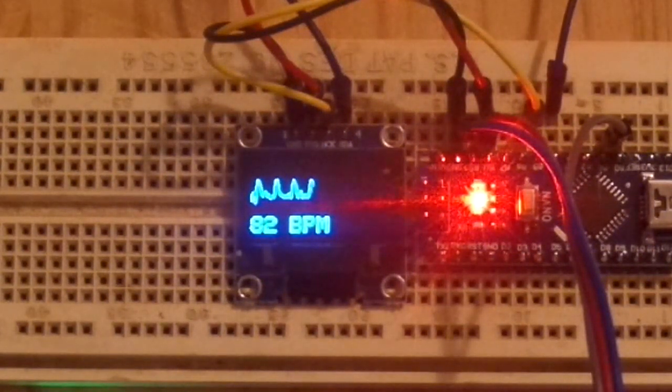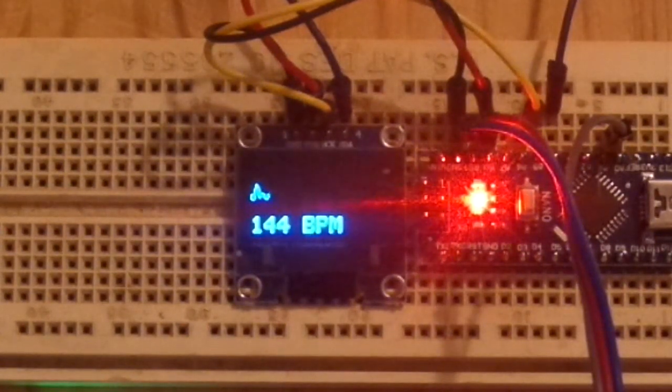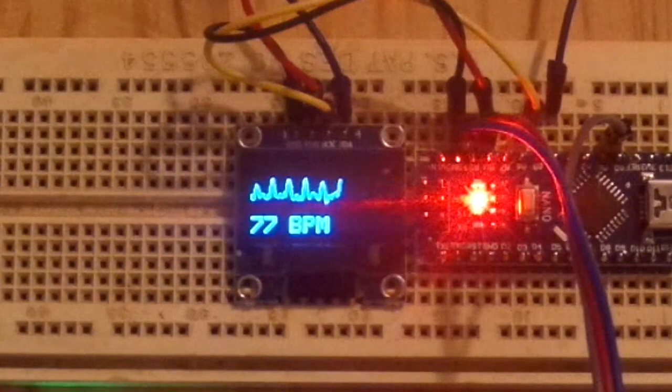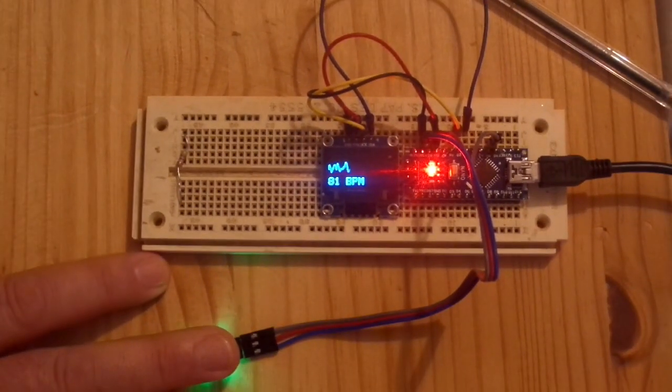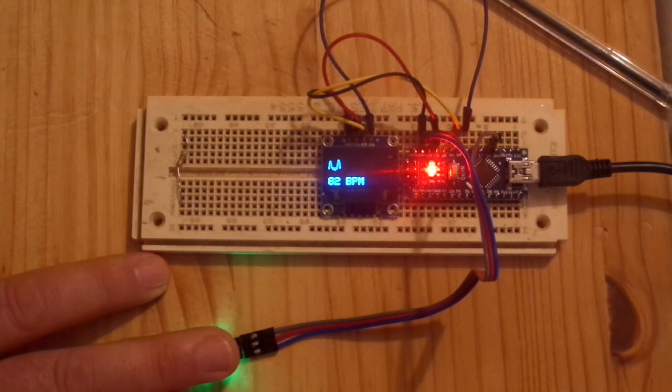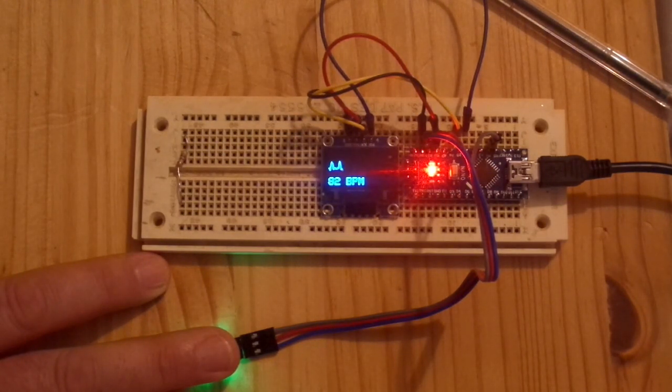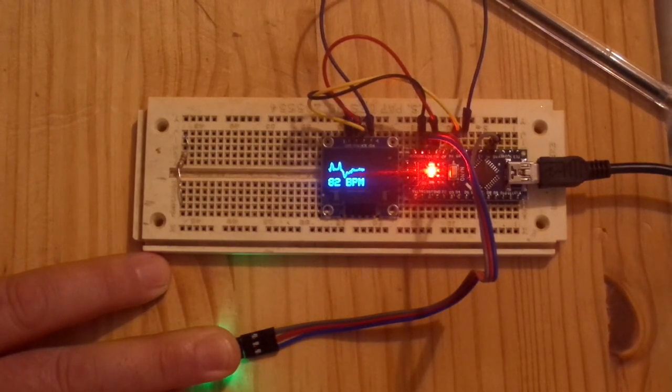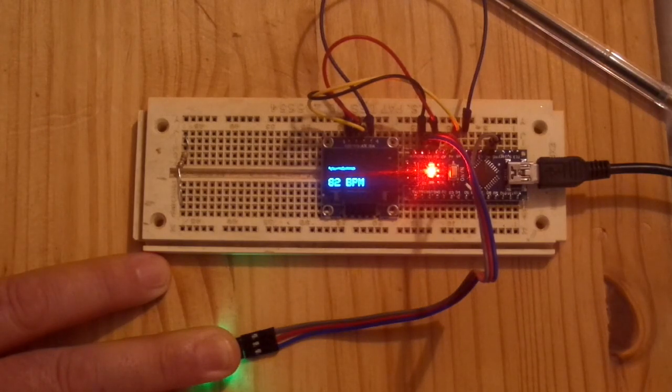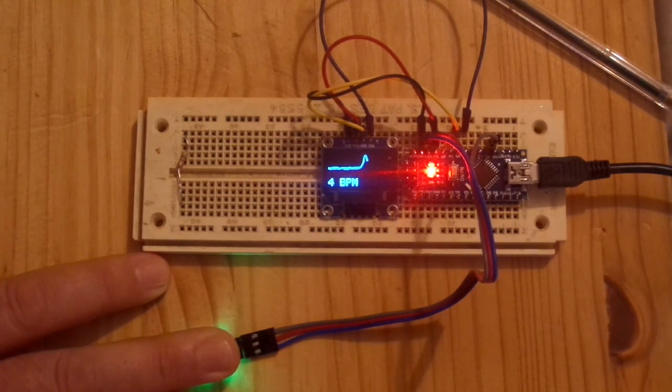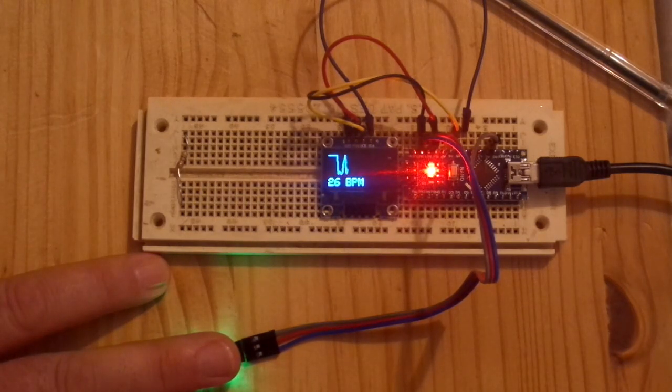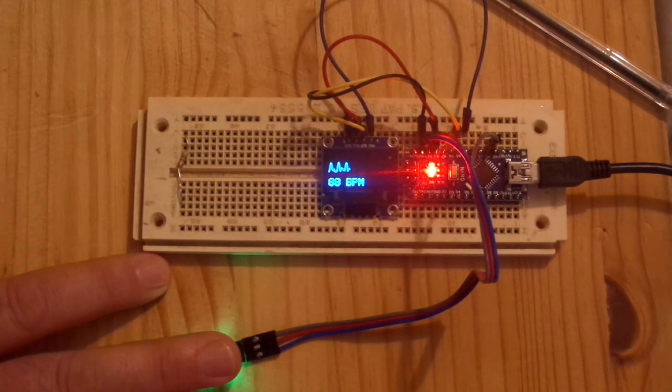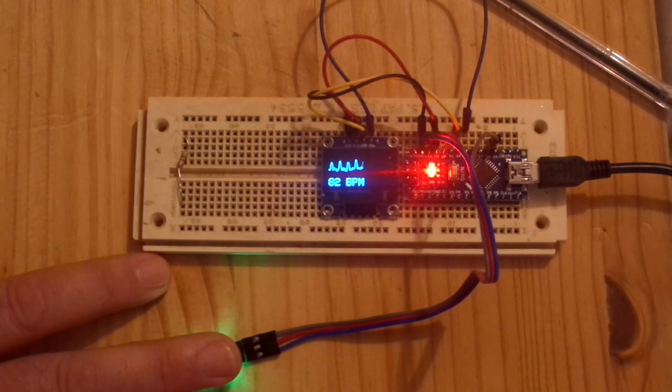So if I start talking again, you can see we're going up into the 80's again. One of the problems with these sensors, they're great for this. It's doing a reasonable job. It's nice to see the trace. If you move your finger a little bit, which is what I'm doing now, you can see it jumps back massively. Even with, I've tried strapping this on with some velcro and some sellotape. If you press too tightly, if you strap it on too tightly, I want to apply some pressure with my finger down onto the sensor now, so it's quite tight. So that's what I've done. I've pressed down on the sensor so it's tight. And obviously what you're doing, you're restricting blood flow in those capillaries. You're squeezing them. And that's the result we get. We get a flat line trace.